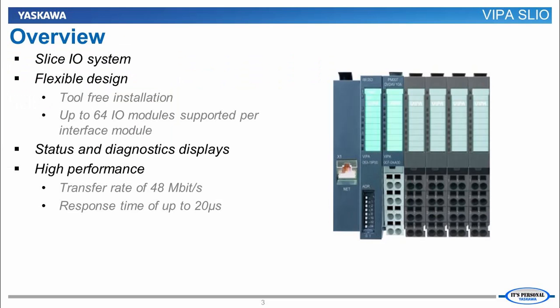The VIPA SLIO system is a SLICE I.O. system which allows the motion controller to have access to external inputs and outputs. The design is very simple so no tools are needed to install it on a DIN rail mount. Each interface module can support up to 64 I.O. modules.